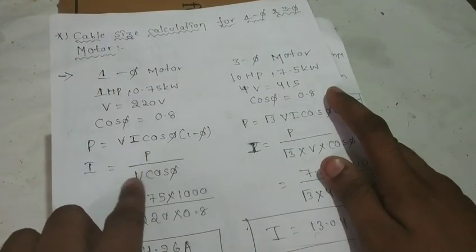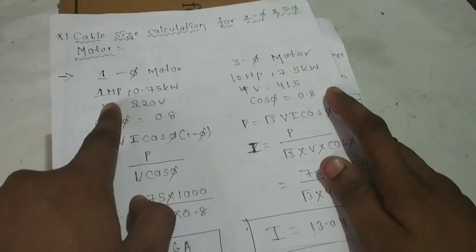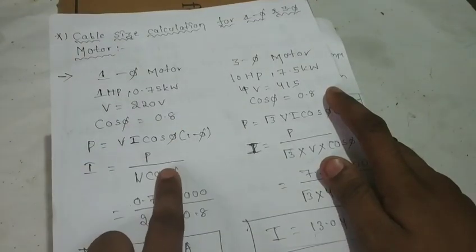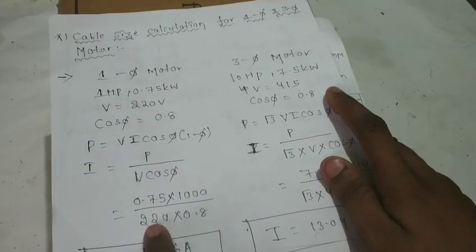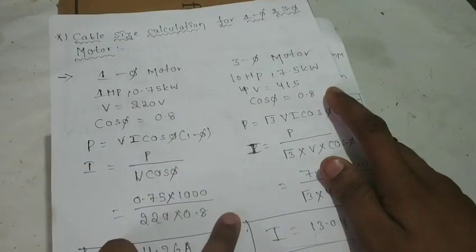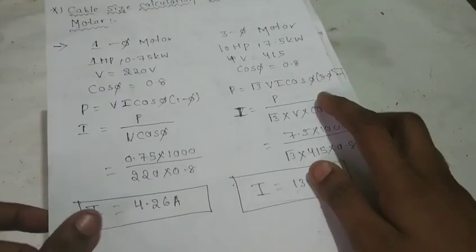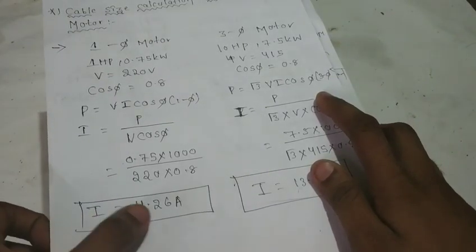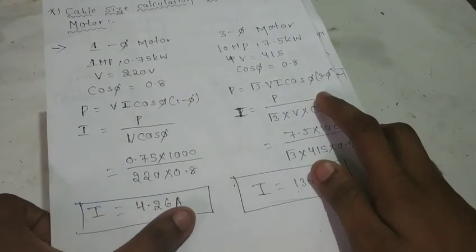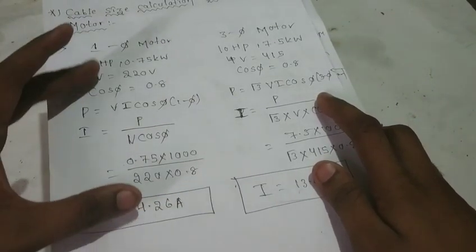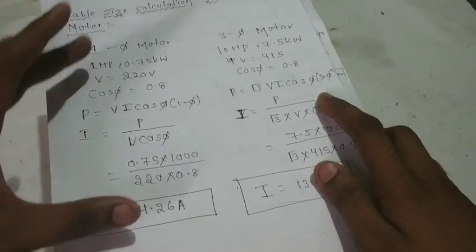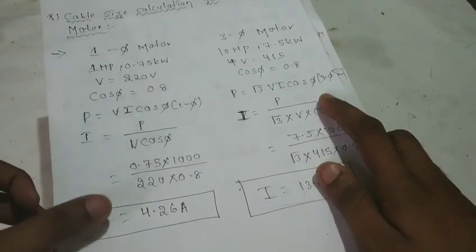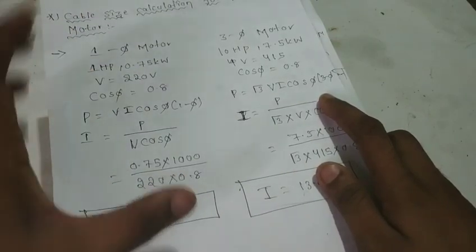This is divided by voltage. Single-phase voltage is 220V. Power factor is 0.8. So the current is equal to 4.26A. This is the motor rated full load current of 4.26A.